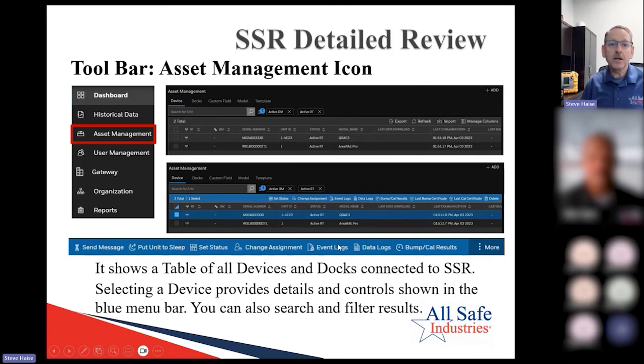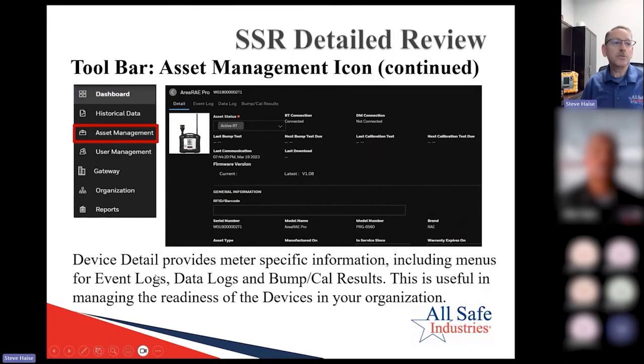You can change assignment to particular users that you have loaded in your software. You can look at event logs, data logs, and bump cal results. If you double click on one of the serial numbers in that asset table, then you get the details of that one particular instrument. You'll see things like its current status, whether it's connected or not.